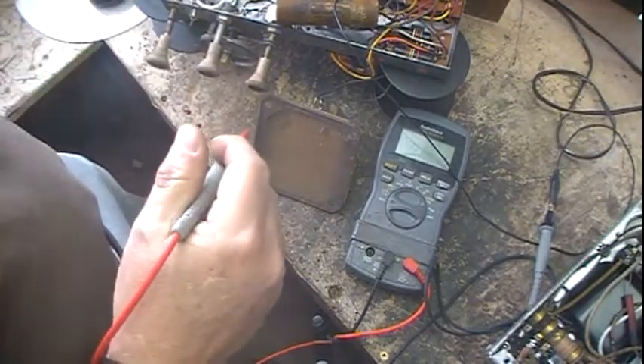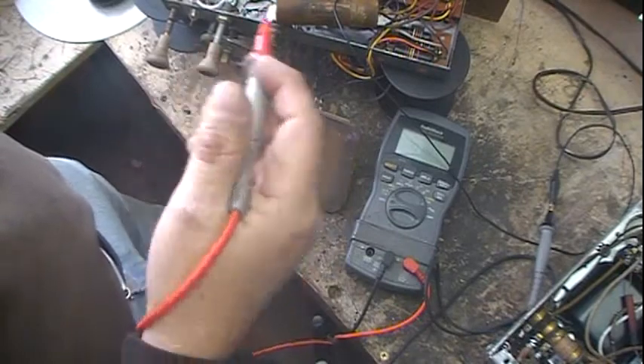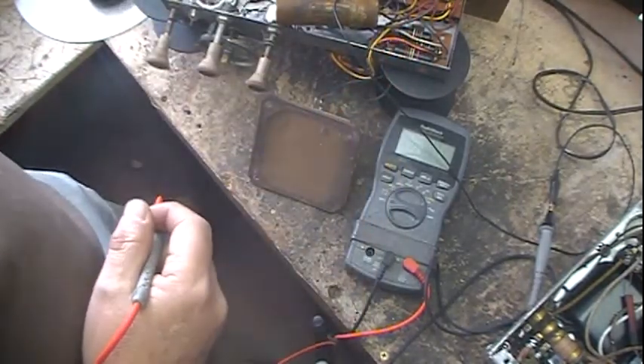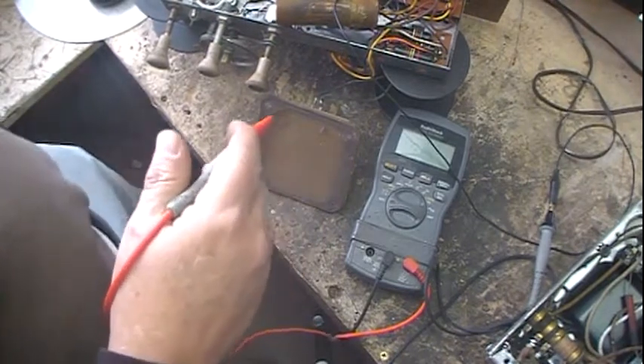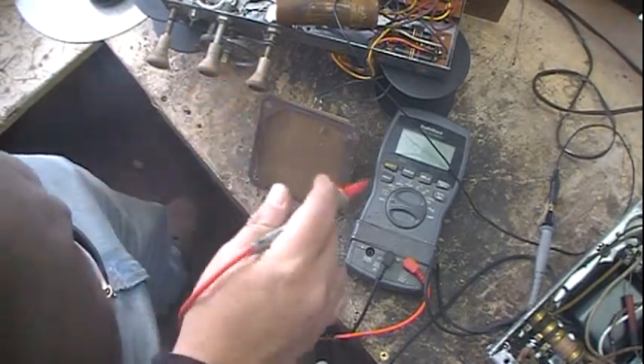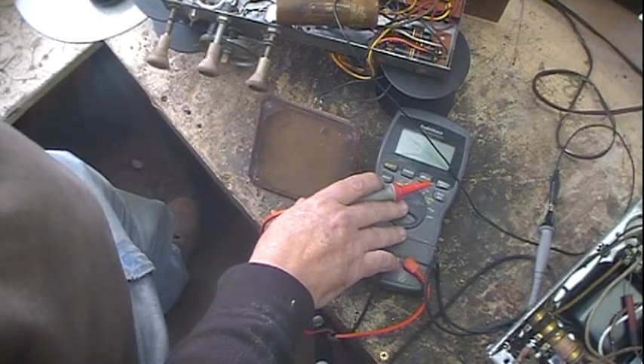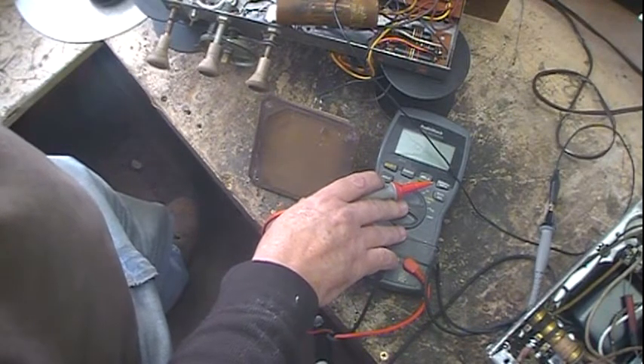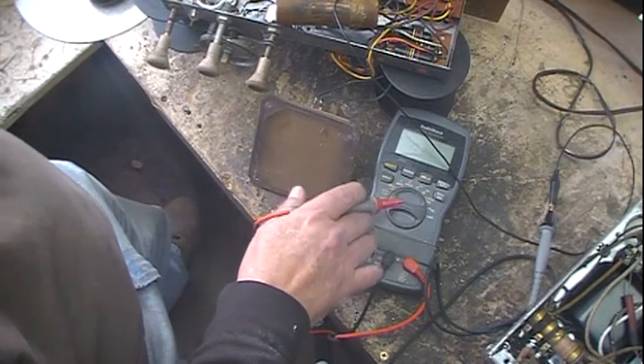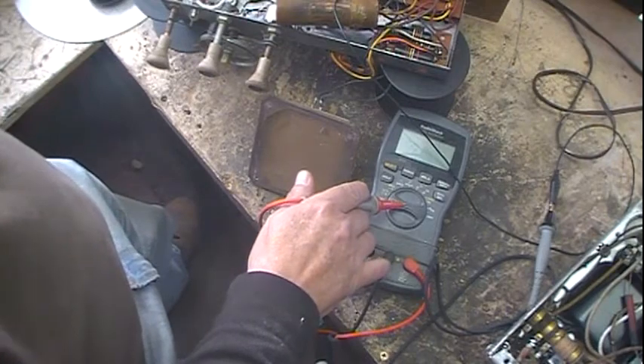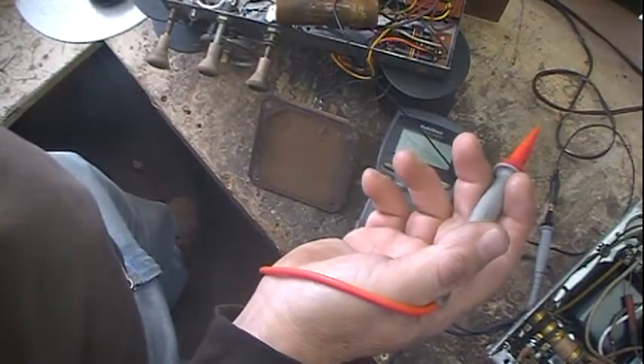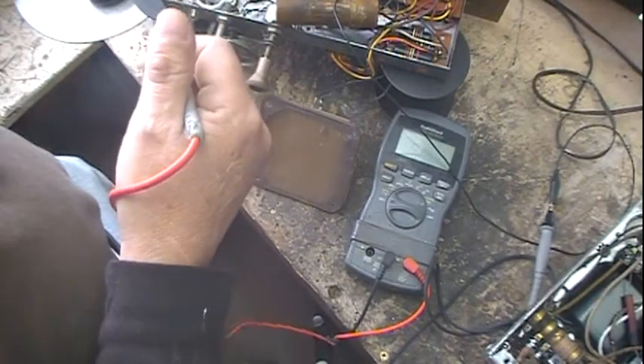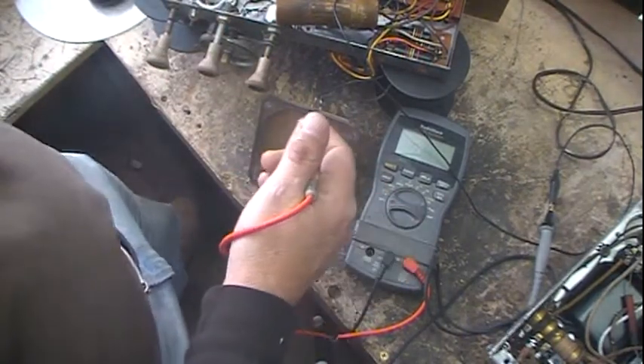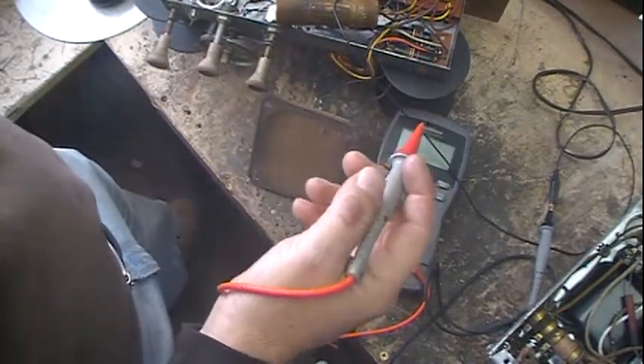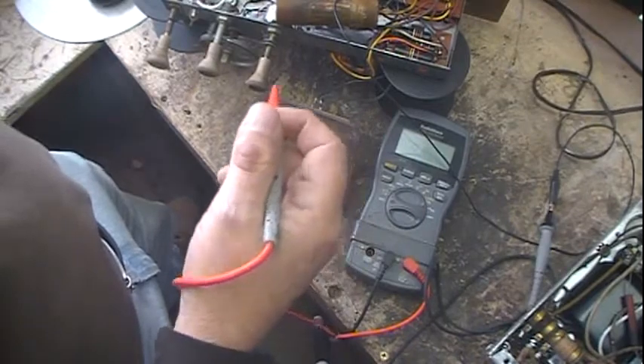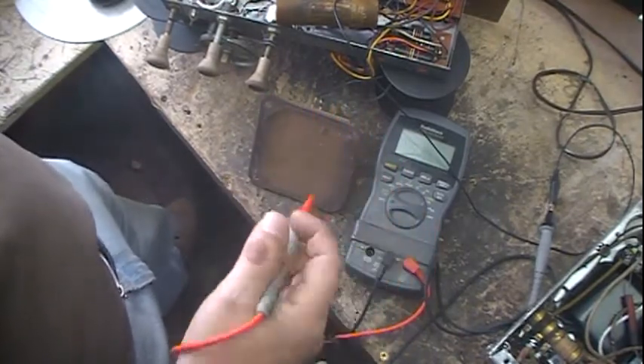If you're checking resistance, you actually do it in reverse of that. It's best to start low and work your way up in ranges. And that brings up the other point about auto ranging when you're not very experienced. Checking resistance, say of a coil or transformer winding, you could have it set where it's too high, where it might show a short and you think the winding is shorted, or too low and it goes out of limits, it calls it open, or OL, and you might think, well, I've got an open coil or open transformer winding.